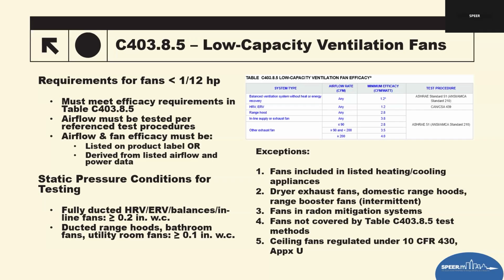Fan efficacy requirements. That efficacy, airflow delivered per watt of input power, is central to this section, just like it is in residential. So the code requires these fans to meet minimum fan efficacy values, preventing the use of basically outdated, inefficient large fans to pull small airflows. Static pressure test conditions to ensure real-world performance.